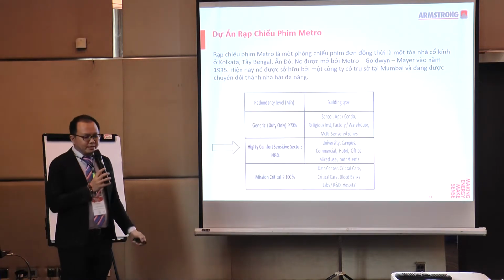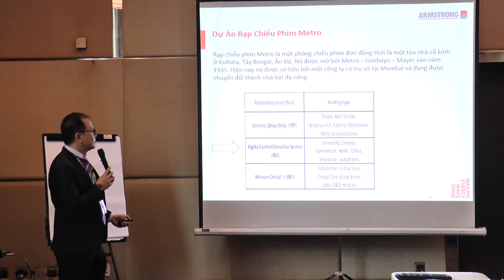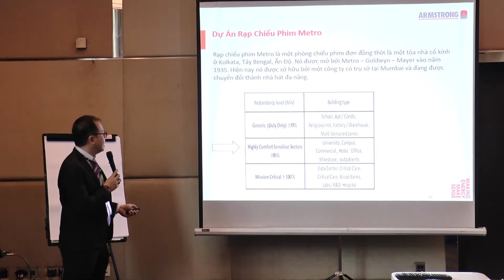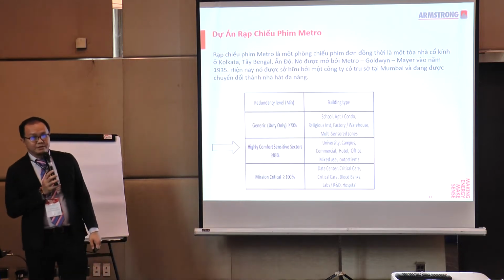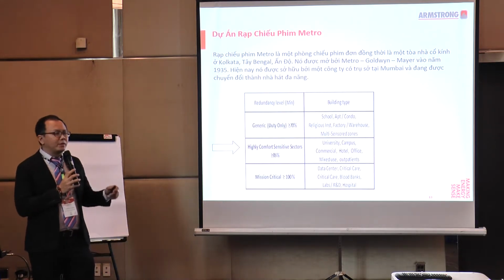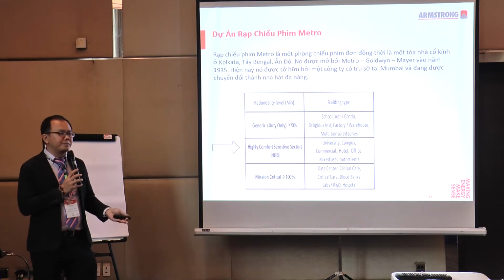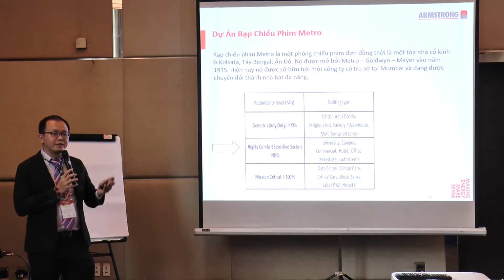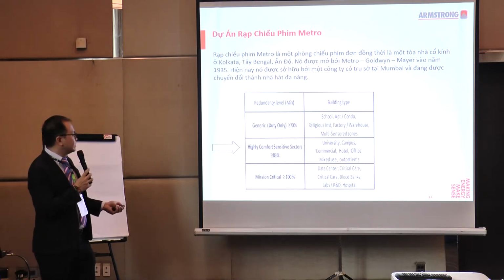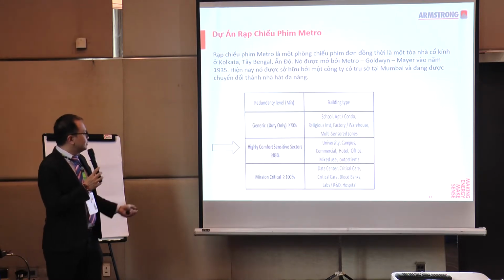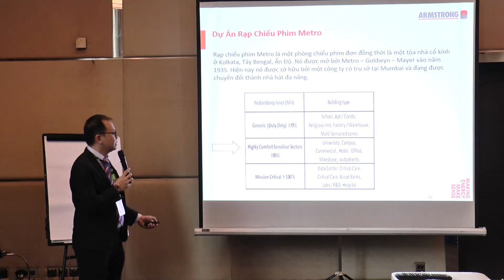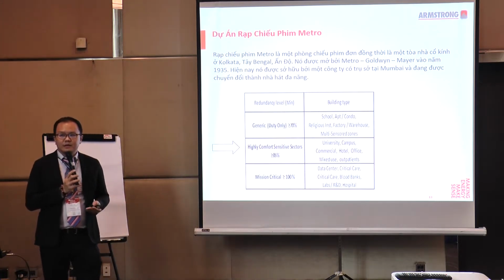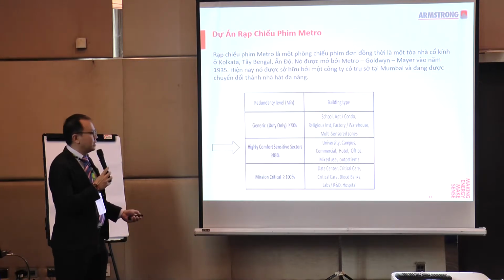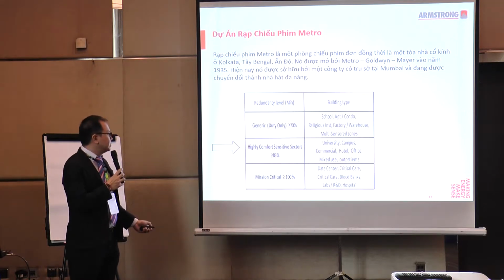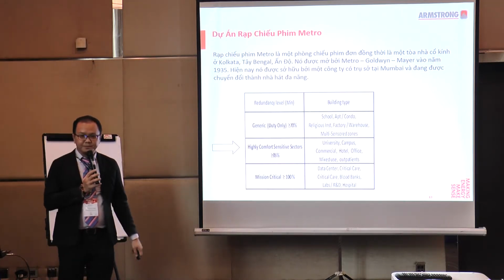But before we talk about this, overall, these cinemas and universities all fall in this category known as the high comfort sensitivity sectors. Earlier you saw the slide about parallel solutions, whether you're running at 50%, 75%, 100% with redundancy. For this type of building, it's usually slightly higher, because you want to maintain the comfort of the people in that building, versus the 100%, which is usually more for data centers and hospital types.